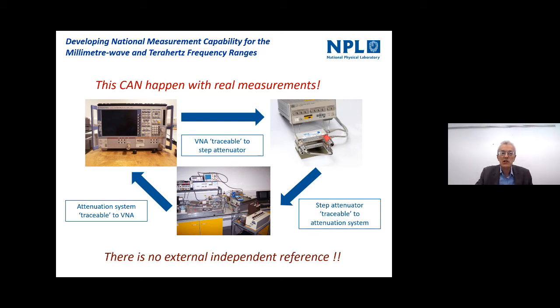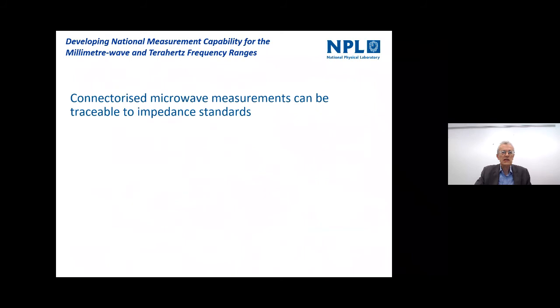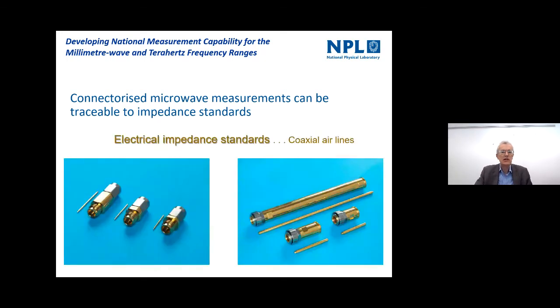They're traceable to each other, but then if there's somebody coming in externally, like a customer for the measurements or a supplier, then the good chances is those measurements will not agree. So how do we deal with that in practice? Well, an alternative method of providing traceability for network analyzers and microwave measurements is to use what we call impedance standards. So this is a different approach for traceability.